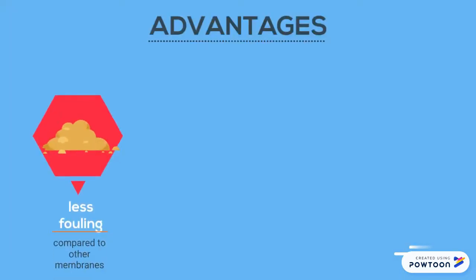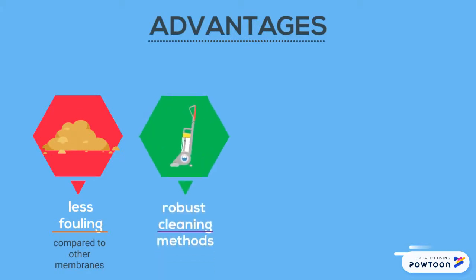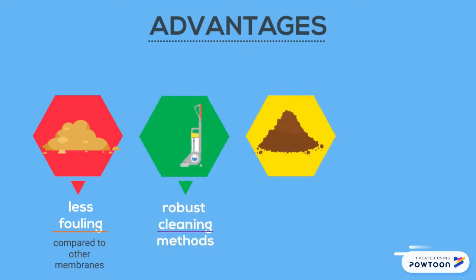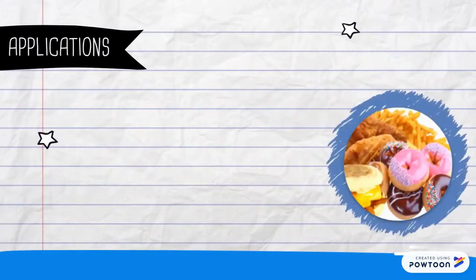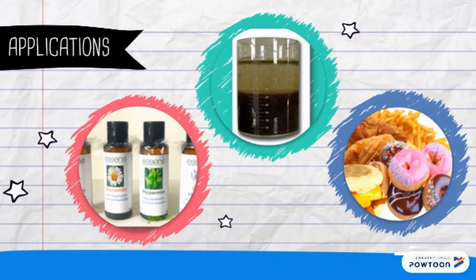Tubular systems have less fouling compared to plate and frame systems. They allow for robust cleaning methods such as the use of harsh chemicals, backwash, and even mechanical cleaning. They can handle the highest solids and emulsified oil load compared to many other membrane types and can be physically cleaned with sponge balls. Common applications include oil-based water treatment, highly suspended solid streams, and lipid and fat processing.